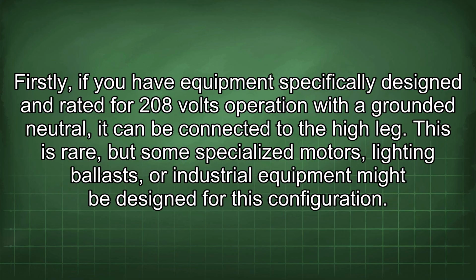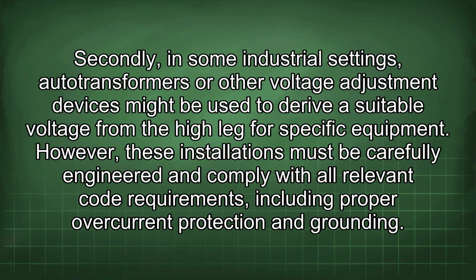Firstly, if you have equipment specifically designed and rated for 208 volts operation with a grounded neutral, it can be connected to the high leg. This is rare, but some specialized motors, lighting ballasts, or industrial equipment might be designed for this configuration. Secondly, in some industrial settings, autotransformers or other voltage adjustment devices might be used to derive a suitable voltage from the high leg for specific equipment. However, these installations must be carefully engineered and comply with all relevant code requirements, including proper overcurrent protection and grounding.